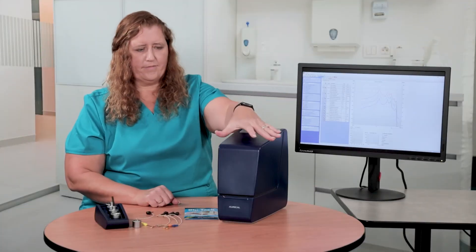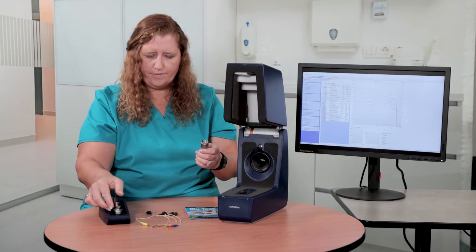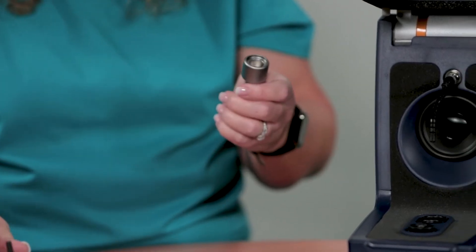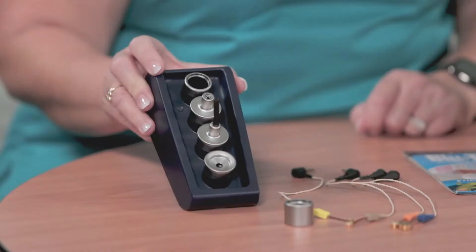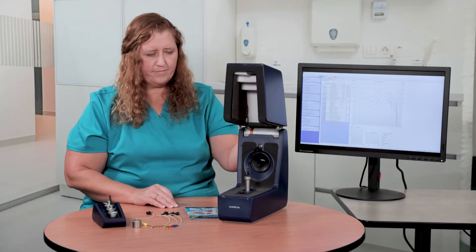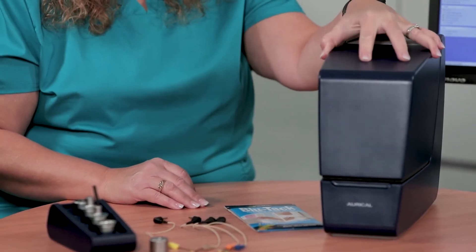The AURICAL HIT test chamber includes all of the tests you need to measure or analyze all types of hearing aids. And even though it's part of the AURICAL system, the AURICAL HIT operates independently of the other AURICAL components. Measure real ear to coupler differences, RECDs, to perform coupler-based fitting for efficiency with both pediatrics and adults.